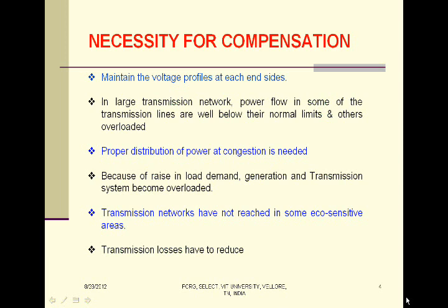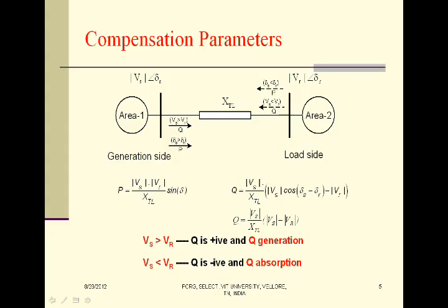Compensators are used to regulate the real and reactive power flow in the system. Consider a two-area system with sending-end voltage Vs and receiving-end voltage Vr, and phase angles dels and delr. With this two-area system, we can frame the real and reactive power flow equations. The real power flow can be controlled by three parameters: voltage magnitude, phase angle, and transmission line reactance. But voltage magnitude and phase angle have some limits and we can't control them to a great extent. So one key parameter we have to control the real power flow is the transmission line reactance. If we increase the transmission line reactance, the power flow will be reduced. If we reduce the transmission line reactance, power flow in the transmission line can be increased.